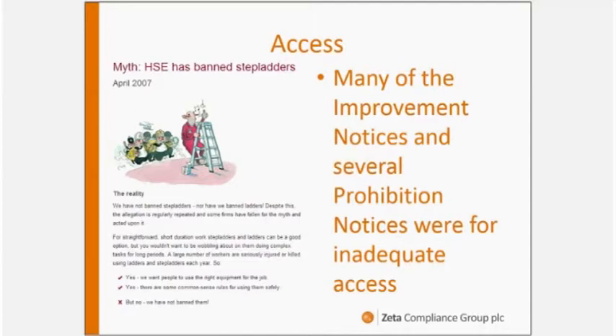And there were several examples where there was no access to inspect the drift eliminators, or to set up or adjust the dosing pumps. And the prohibition notice said, you can't run this system safely because you don't have a safe practice, safe access, or a specific task. Shut the thing down. Stop using it. Okay, well, that's an interesting finding, I think.